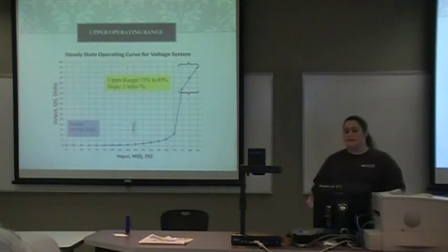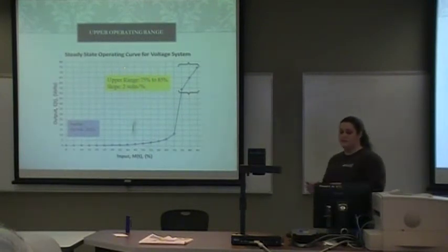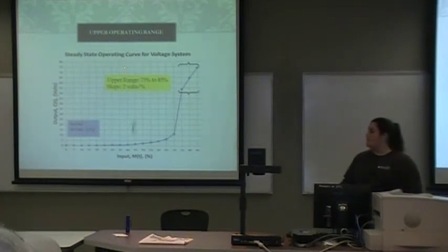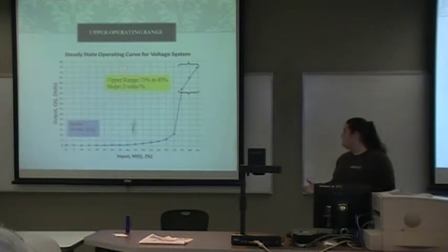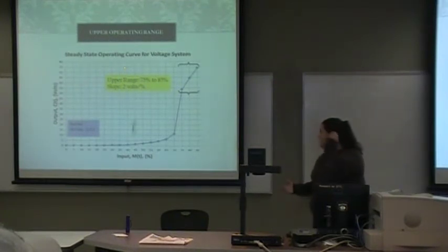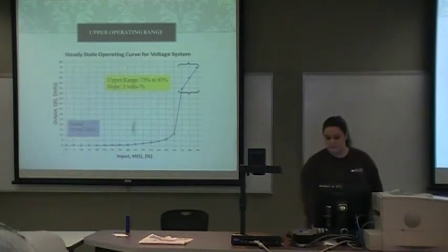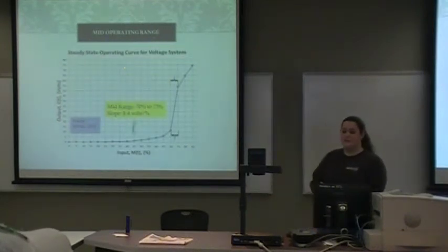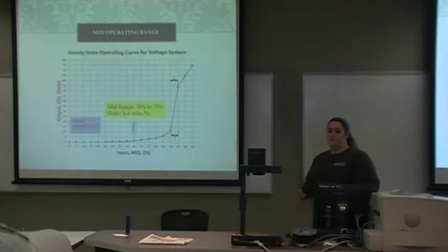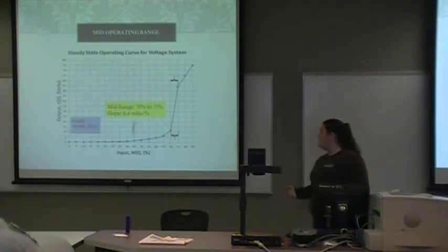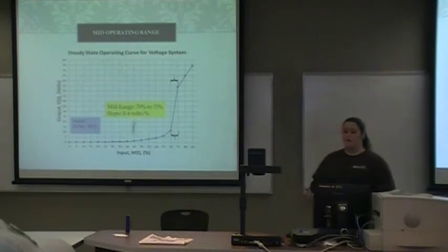This is the upper range for our system. In this range it's linear, from 75% to 85%, and the slope is 2 volts per percent input. The mid-range is 70% to 75%, and the slope of this region is 8.4 volts per percent input.